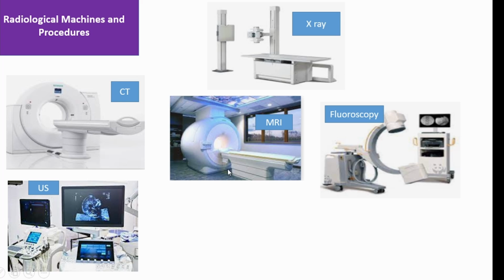With magnetic resonance imaging, the major precaution is you must make sure that you don't take metallic couches in here, or your coins, or bring a patient with metallic objects, be it implants like pacemakers. This has very powerful magnets, the higher Teslas. So when you bring a metallic object, it's going to fly. If you are bringing a patient on a couch, it can fly into the gantry of the MRI machine. It can even kill a patient who is on a pacemaker. So those are the precautions that one has to take when taking a patient to an MRI room.